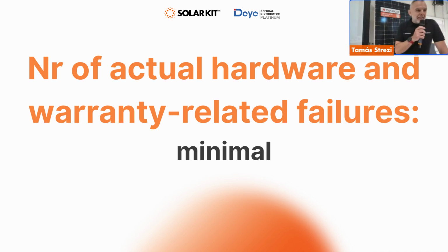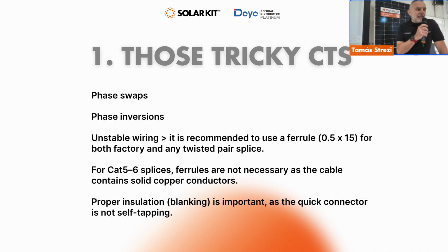The Achilles heel, if you will, of the Deye system is the CTs and their setup. What I already mentioned, that the CTs have to match the grid phases exactly, is pretty much the most basic mistake made. And you shouldn't just blindly follow the product brochure about the installation, because there was a series of CTs where the directions were reversed. So black and white may not be black and white, and the arrow may not point in the right direction. But this is something that you can check at the inverter immediately during the installation.